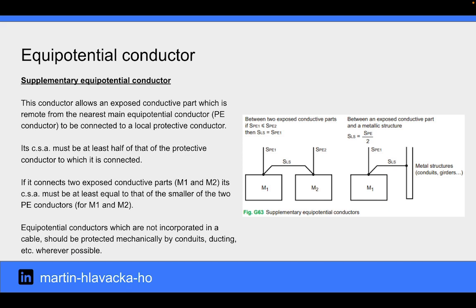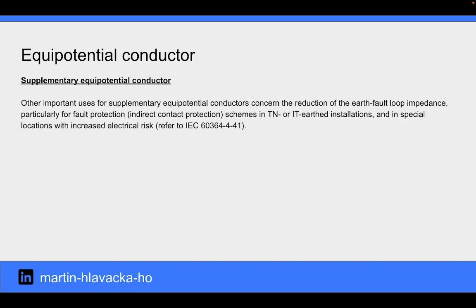Equipotential conductors which are not incorporated in a cable should be protected mechanically by conduits, ducting, etc. wherever possible. Other important uses for supplementary equipotential conductors concern the reduction of the earth fault loop impedance, particularly for fault protection schemes in TN or IT earthed installations, and in special locations with increased electrical risk.